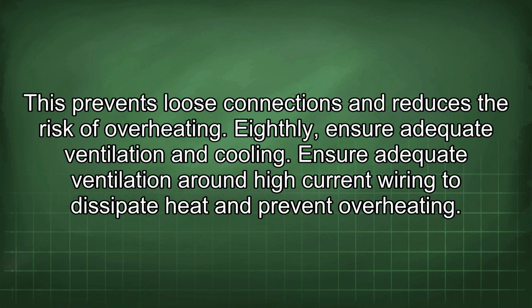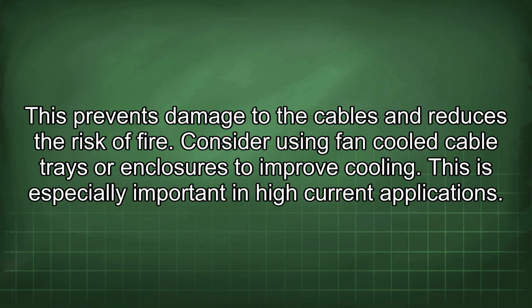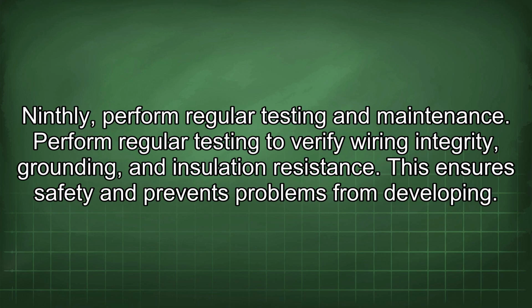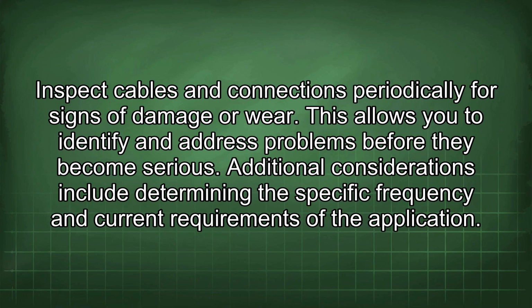Eighthly, ensure adequate ventilation and cooling. Ensure adequate ventilation around high current wiring to dissipate heat and prevent overheating. This prevents damage to the cables and reduces the risk of fire. Consider using fan-cooled cable trays or enclosures to improve cooling. This is especially important in high current applications. Ninthly, perform regular testing and maintenance. Perform regular testing to verify wiring integrity, grounding, and insulation resistance. This ensures safety and prevents problems from developing. Inspect cables and connections periodically for signs of damage or wear. This allows you to identify and address problems before they become serious.